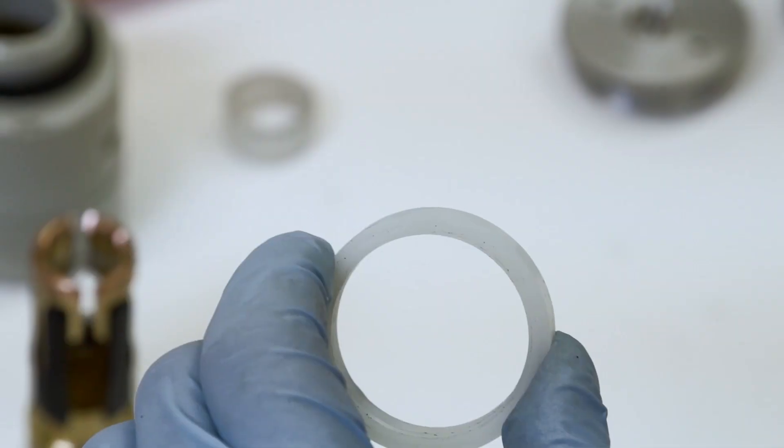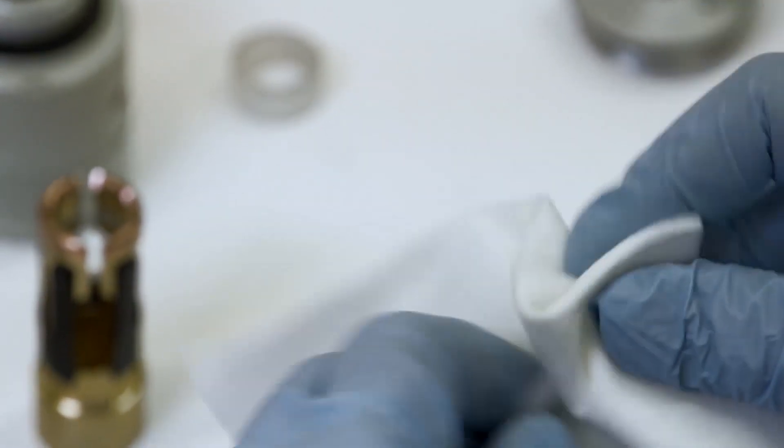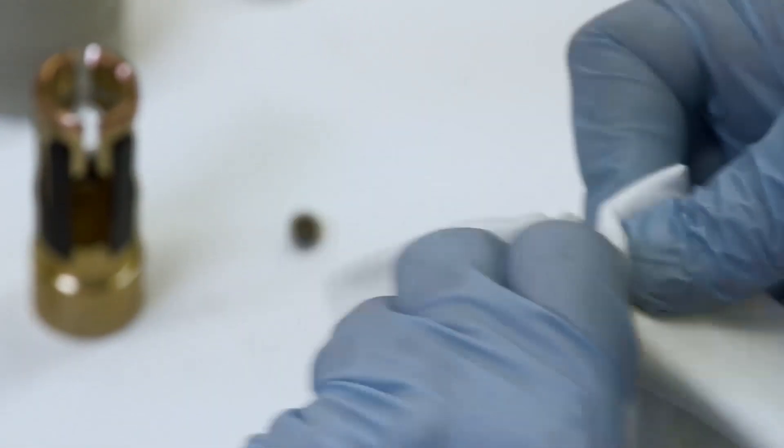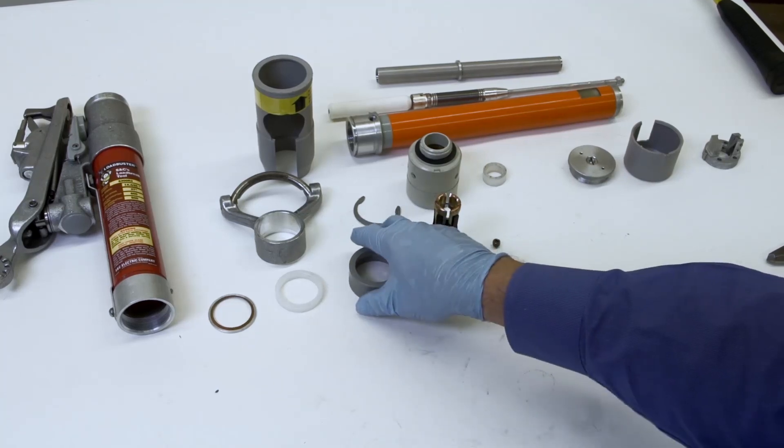Then look at the bearing and bearing retainer for evidence of damage. Clean with the soft cloth. Replace if necessary.